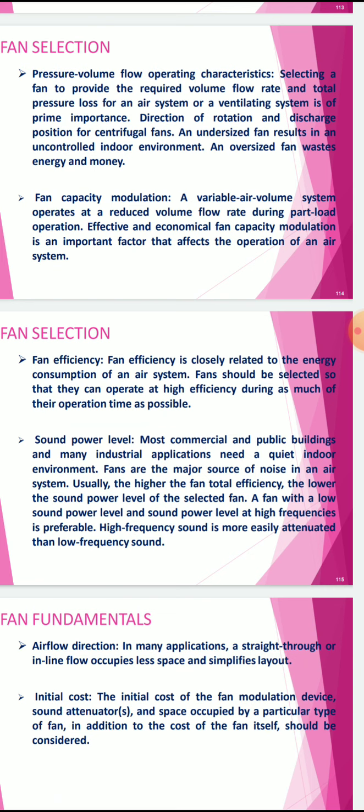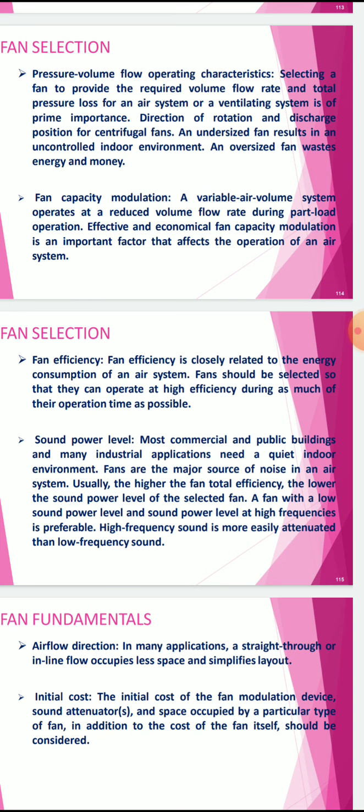Therefore, the higher the fan total efficiency, the lower the sound power level of the selected fan. A fan with a low sound power level at high frequencies is preferable. High frequency sound is more easily attenuated than low frequency sound.